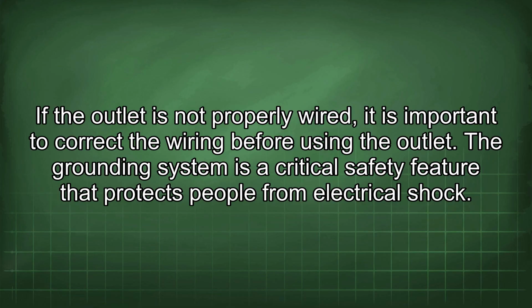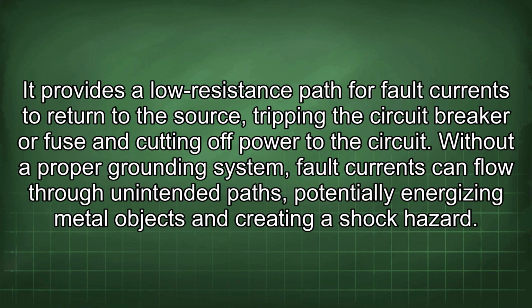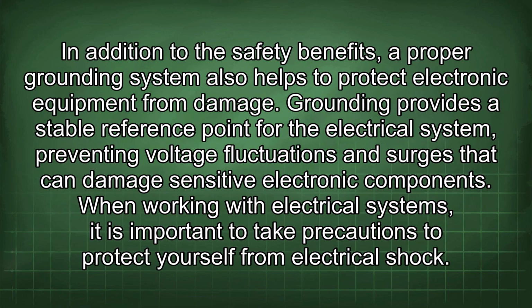The grounding system is a critical safety feature that protects people from electrical shock. It provides a low resistance path for fault currents to return to the source, tripping the circuit breaker or fuse and cutting off power to the circuit. Without a proper grounding system, fault currents can flow through unintended paths, potentially energizing metal objects and creating a shock hazard. In addition to the safety benefits, a proper grounding system also helps to protect electronic equipment from damage.